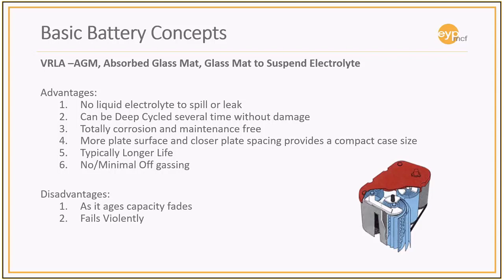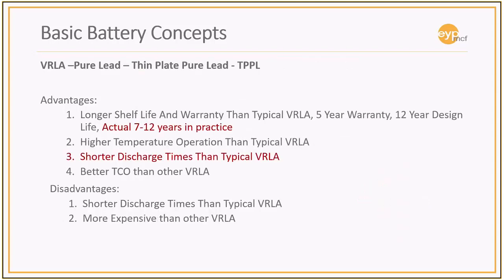So in the absorbed glass mat, same type of disadvantages. The biggest issue really is that violent failure. Pure lead. We're seeing a big move towards the pure lead environment. The technology that's available now gets you a slightly longer design life, but allows you to get a shorter time. There's an effect called coup de fouet, a French term. It basically means that you can only go so short with these batteries, and then there's no time. So you can take a pure lead battery down to 5 minutes initially, and over time it will degrade to 3 to 2 minutes.